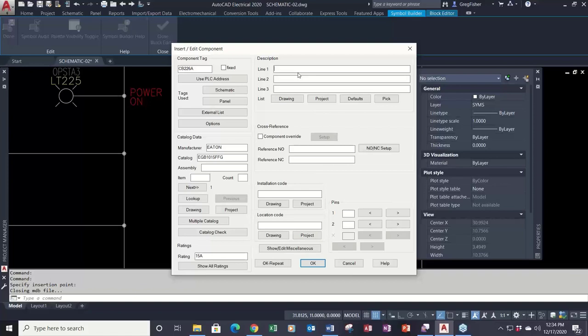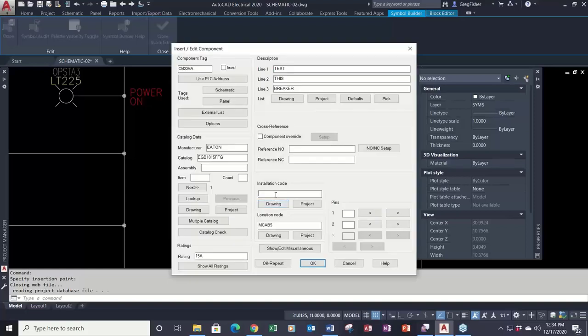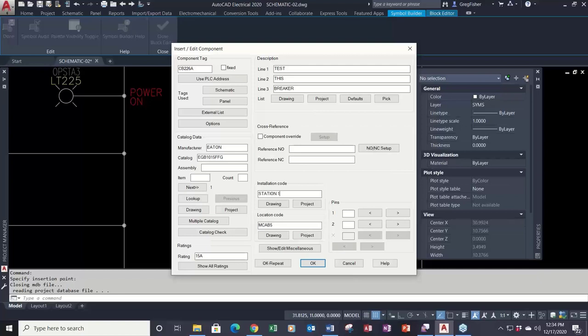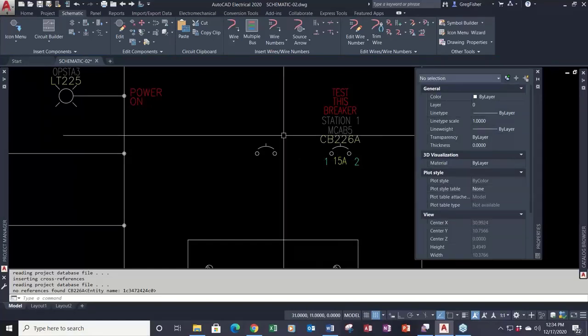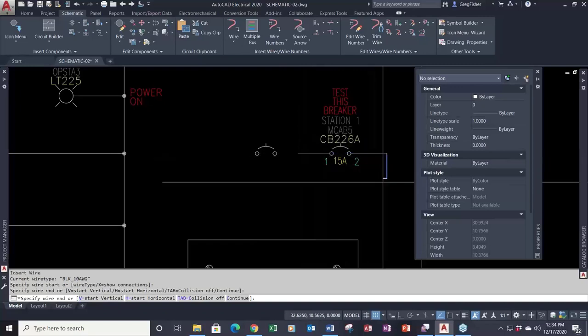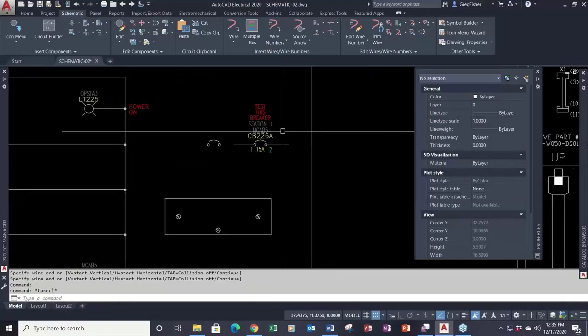The catalog number is driving the rating. I have three lines of descriptions — remember I added that third attribute on my own. I'll type something in for the description and add a location code and installation, just to see where my text ends up. The pin numbers — the catalog number didn't have predefined pin numbers, so I can fill in terminal numbers. The last big test is to draw a wire through it to confirm the connection points work. That's how we create an AutoCAD Electrical intelligent block from scratch.